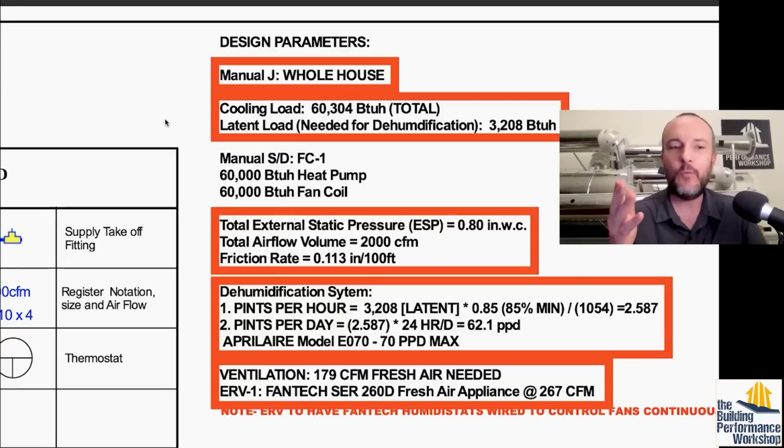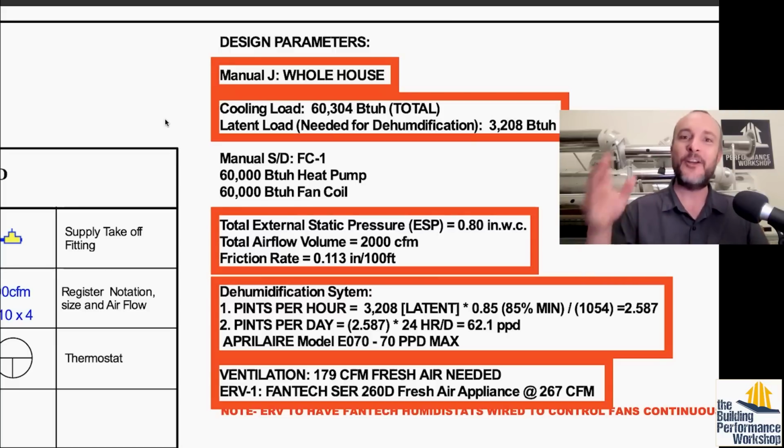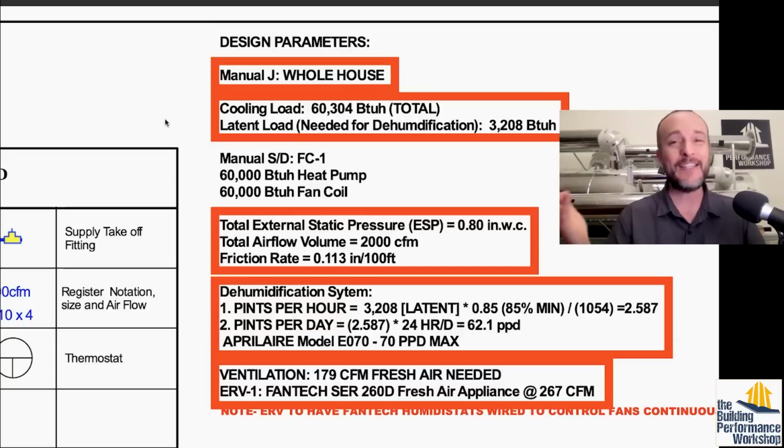That means that we did not get the amount of BTUs that are needed by each room. So that's why that powder room is getting 14, because they just divvied it up proportionally based on the square footage compared to the house, not based at all on the actual load of each room. So it's possible that some rooms that have lots of windows that face the wrong way, meaning for the sun, are going to be undercooled in the summer at that certain time when the sun is coming in through them, and that other rooms are going to be overcooled, and likewise, vice versa in the wintertime.